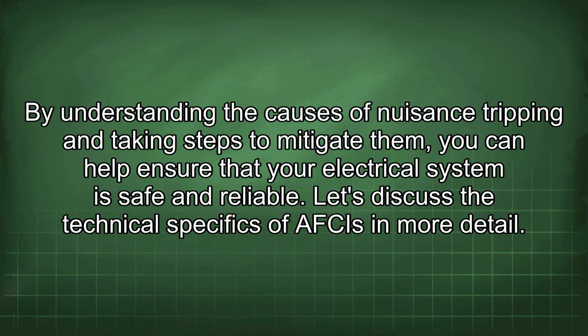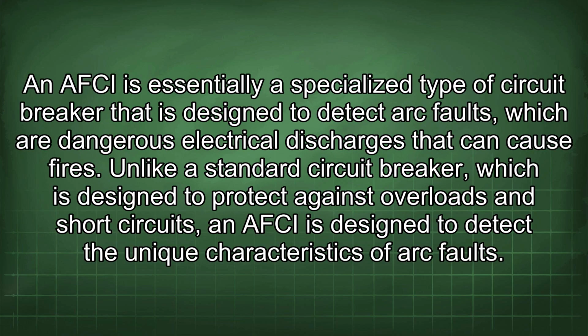Let's discuss the technical specifics of AFCIs in more detail. An AFCI is essentially a specialized type of circuit breaker that is designed to detect arc faults, which are dangerous electrical discharges that can cause fires. Unlike a standard circuit breaker, which is designed to protect against overloads and short circuits, an AFCI is designed to detect the unique characteristics of arc faults.